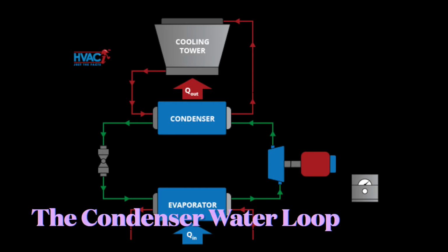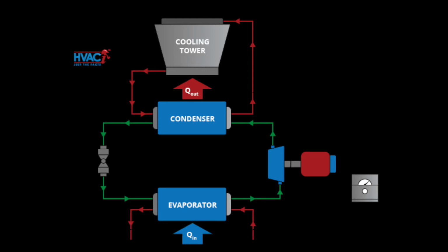The condenser water loop is an open loop system taking place between the condenser in the chillers and the cooling tower. Heat is transferred into the atmosphere, which means it has left the cycle, and the cycle contains non-potable water. The condenser water found inside the chiller cools down the newly heated refrigerant. The newly heated condenser water travels up to the cooling tower. Once there, airflow and evaporation cool down the condenser water, and this newly cooled condenser water returns back to the chiller.